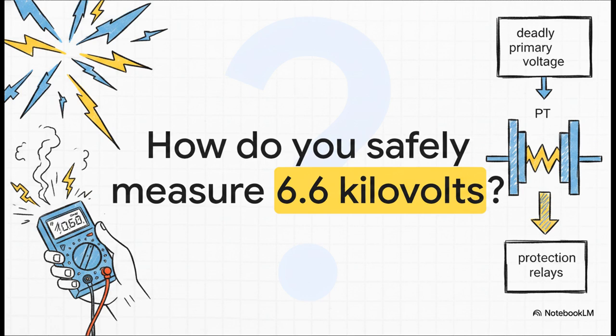You absolutely cannot just slap a standard multimeter directly across a live marine busbar. The sheer energy would literally vaporize the equipment and potentially the technician holding it, which is obviously a no-go. We need a way to step that massive voltage down to a safe, readable level without losing the accuracy of the measurement, all while keeping a solid physical barrier between that deadly primary voltage and our sensitive protection relays.